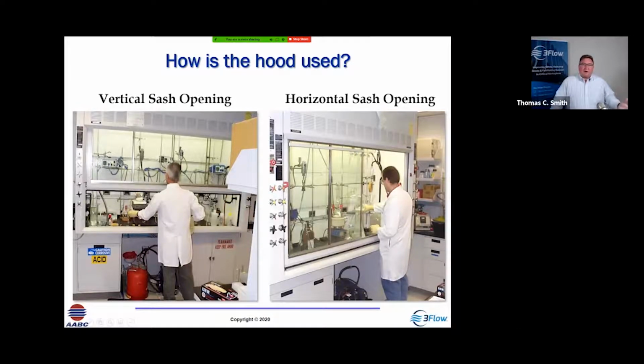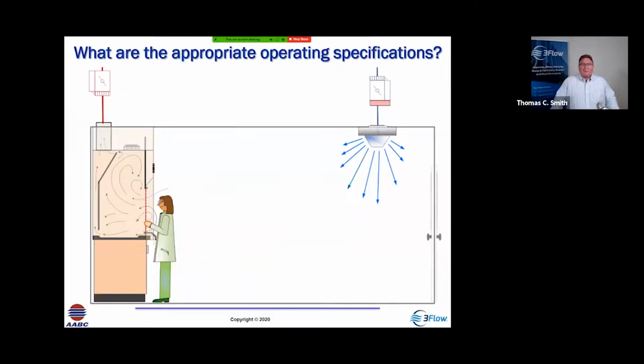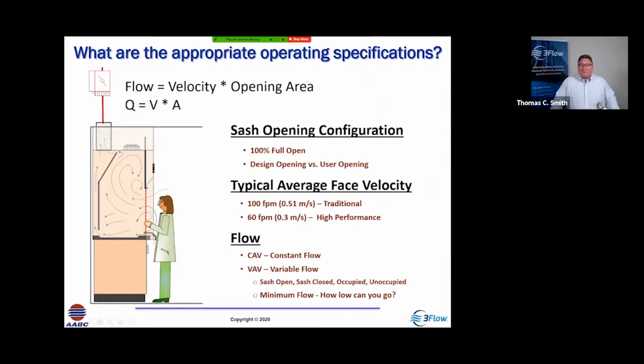Those are different operational configurations, so every hood that has multiple or combination sashes has to be tested in both configurations. We need to evaluate what are the appropriate operating specifications. Q equals VA, velocity times area equals exhaust flow. But that's not the only question. We need to know what is the sash opening configuration. What is the average face velocity required for proper operation?